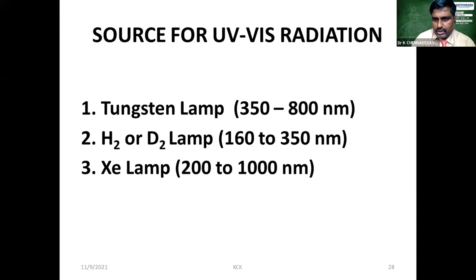Among these, the xenon lamp is expensive and has a short lifetime, but the remaining tungsten lamp and hydrogen lamp have quite a good lifetime. So even if you want to see the entire UV visible radiation, we can make an exchangeable light. That means we will be keeping both lamps, the tungsten lamp and the hydrogen lamp. So it will be scanning from 160 nanometers to 800 nanometers. With the tungsten lamp itself we cannot go from 200 nanometers to 800 nanometers, so we can club it with either a deuterium or hydrogen lamp.